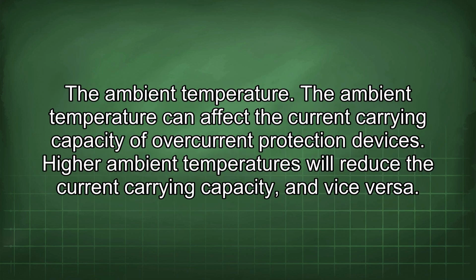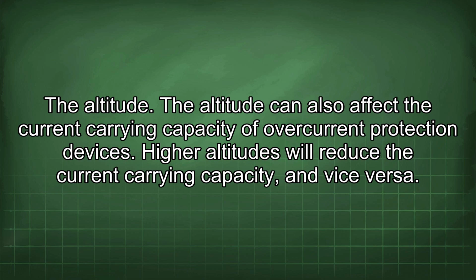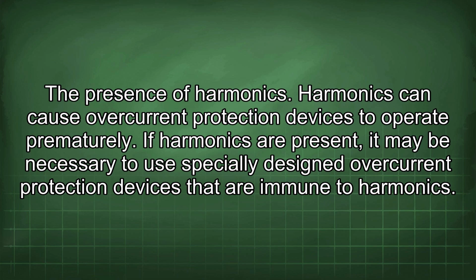The ambient temperature. The ambient temperature can affect the current carrying capacity of overcurrent protection devices. Higher ambient temperatures will reduce the current carrying capacity, and vice versa. The altitude. The altitude can also affect the current carrying capacity of overcurrent protection devices. Higher altitudes will reduce the current carrying capacity, and vice versa. The presence of harmonics. Harmonics can cause overcurrent protection devices to operate prematurely. If harmonics are present, it may be necessary to use specially designed overcurrent protection devices that are immune to harmonics.